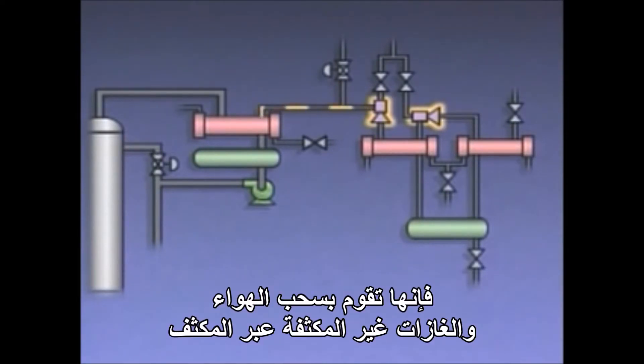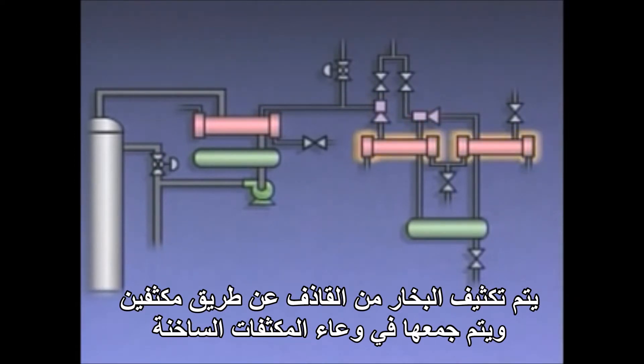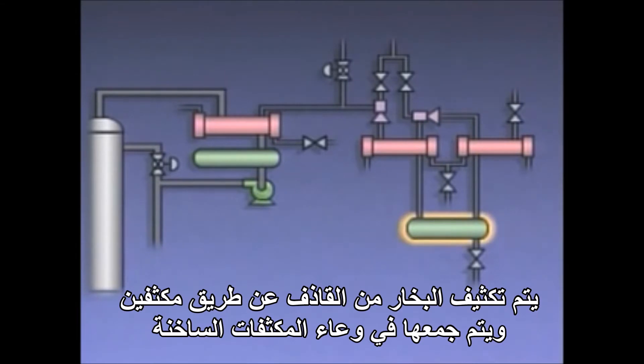The steam jets draw air and other non-condensable gases from the condenser. The steam from the jets is condensed in these two condensers and collected in a condensate hot well, while the air and non-condensable gases leave the system through a vent line.